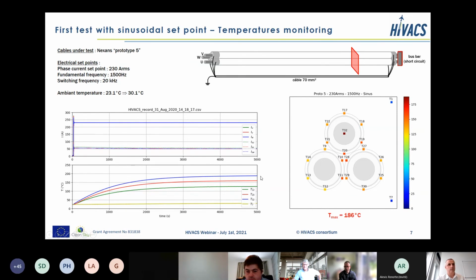And you see in this graph that the blue one is the highest temperature, 186 degrees C in this test, and the red and the green curves are the maximum and minimum temperature on the surface of the three-fold configuration. So you can see there is quite a strong gradient between the maximum temperature in the conductor and the minimal temperature.